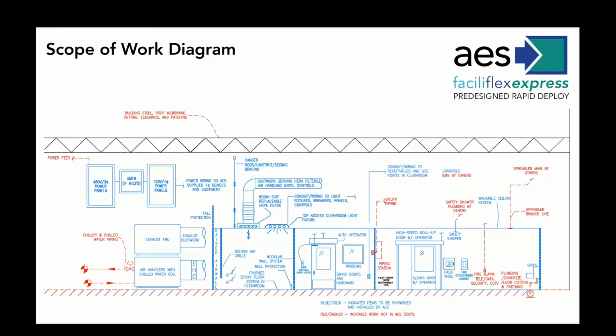Without belaboring the point, there's an advantage because you have these modular, sub-modular designs of the HEPA filter modules. Whether you have the 5K or 15K or whatever, you probably have pretty much standard modules. There seems to be an advantage, from a maintenance standpoint, of a facility moving from a smaller unit to a bigger unit while using some of the same technology.